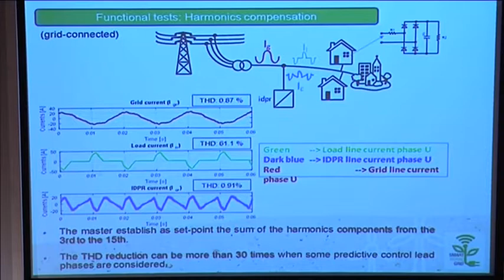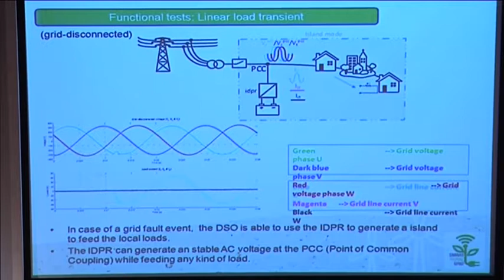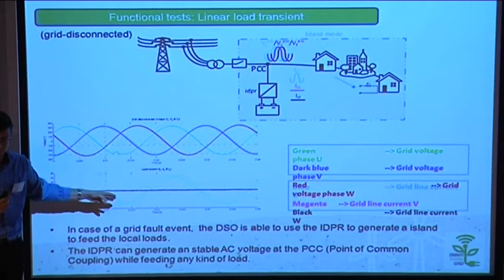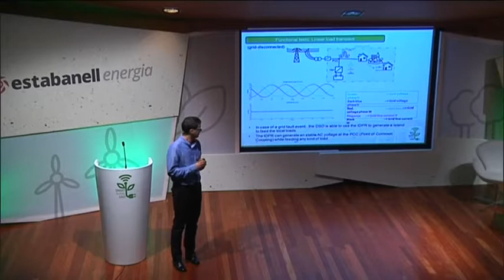These are also in the lab. In this case, these three waveforms represent the three voltages, and then we connect, in the worst case, more or less at the peak in terms of current, a heavy load. The IDPR is based on power electronics, so we don't have the mechanical inertia that we would have if we were generating with a rotary machine. So we need to supply that current in a really fast way in terms of voltage, because the load will otherwise see a dip or a sag depending on if we connect or disconnect the load. As you can see here, we are able to support that heavy consumption with just a really fast transient in terms of voltage. This is good because we are supplying inertia in terms of current.